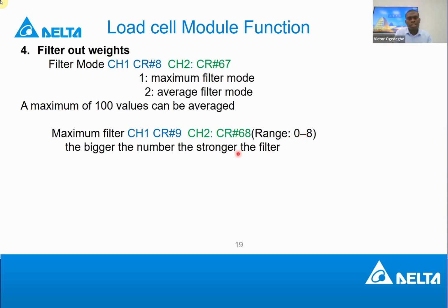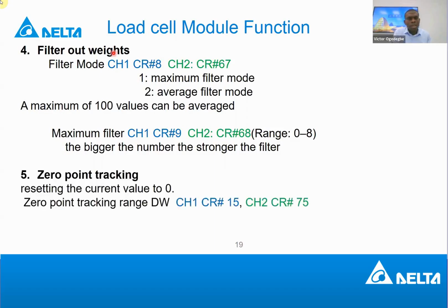So this is just filtering the signal that is being measured. The bigger the number, the stronger the filter. So if you specify 7 in this register, it means for this sensor, I'm measuring channel 1, and I'm filtering based on this magnitude. So you can filter out noise that you don't want, so that your measurement from the sensor is smooth. And then another function, again, zero point tracking.